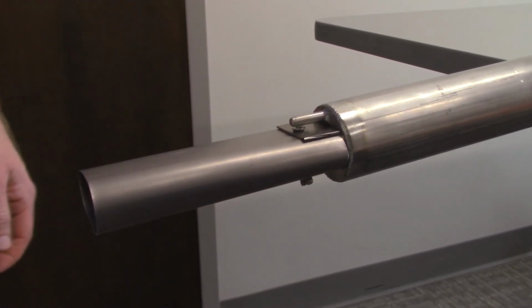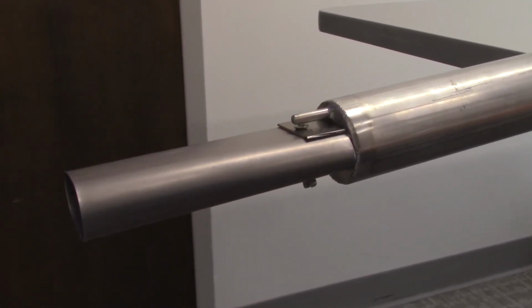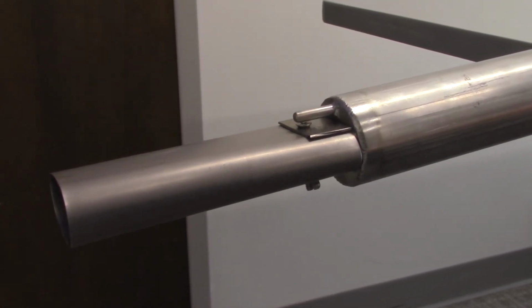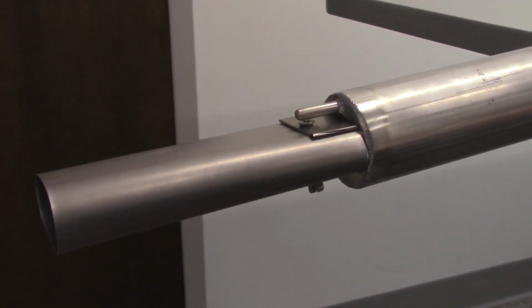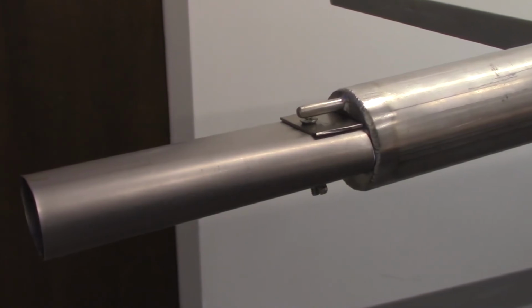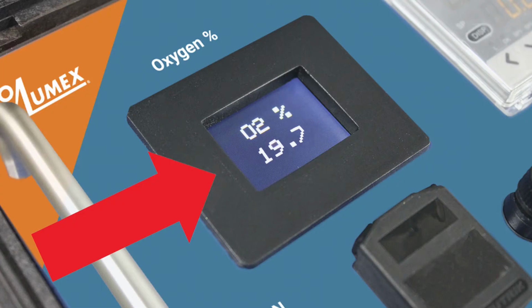Now keep in mind, the probe shield is not appropriate for all applications. We recommend you contact us to discuss your specific application in order to determine whether it is appropriate to use the shield. As an option, OLM30B sampling systems may include an oxygen sensor. This is useful if measuring the same analyte at multiple locations in a process stream, or if the measurements must be expressed on an oxygen-corrected basis.